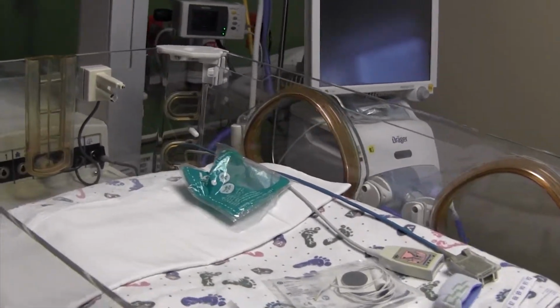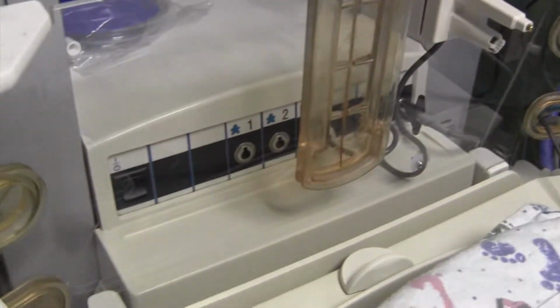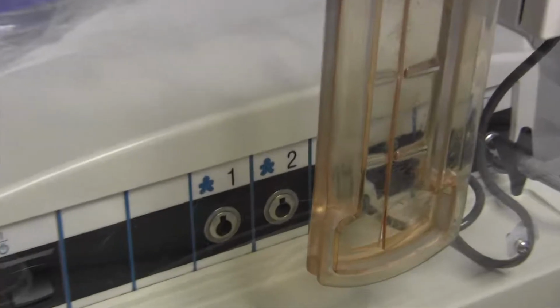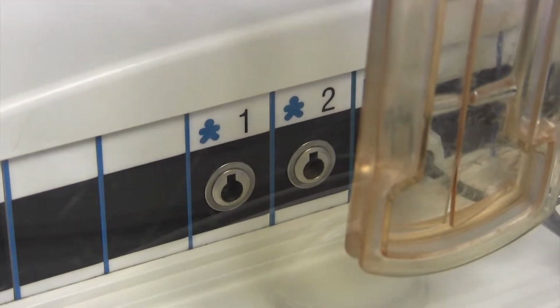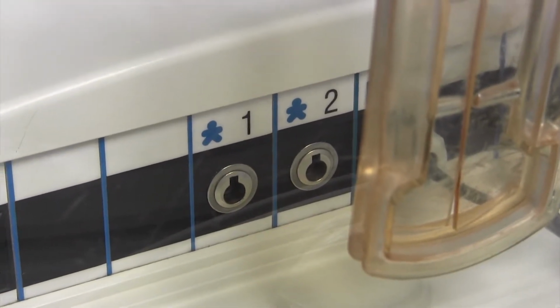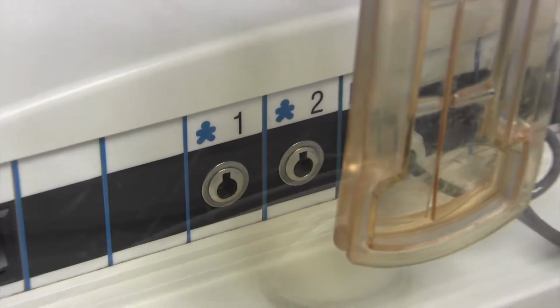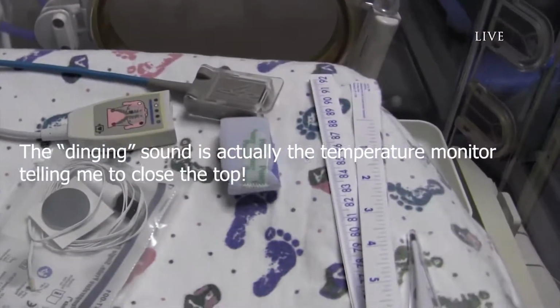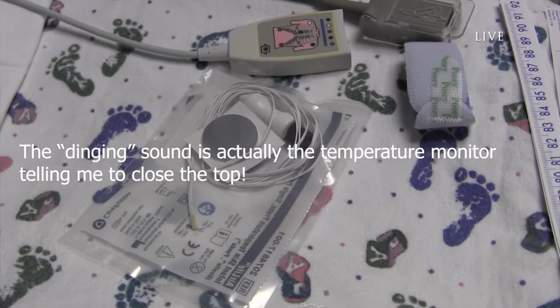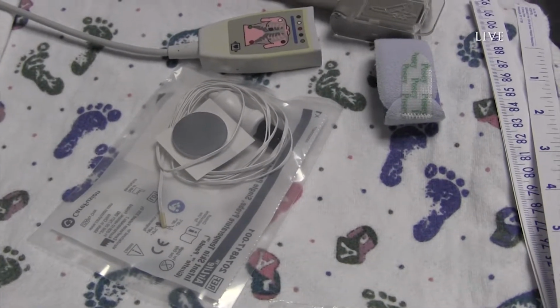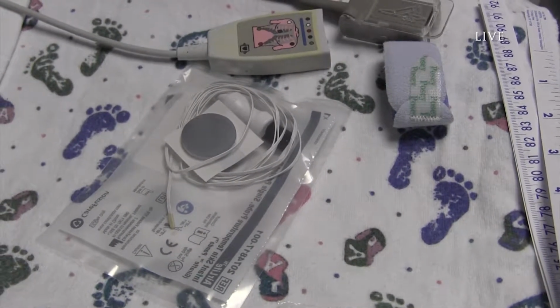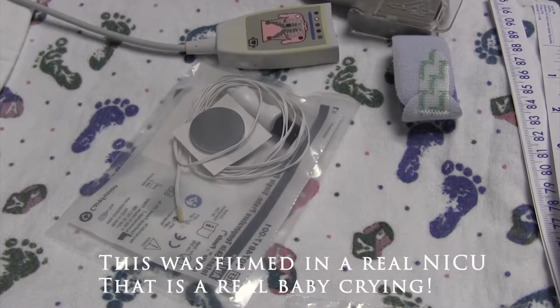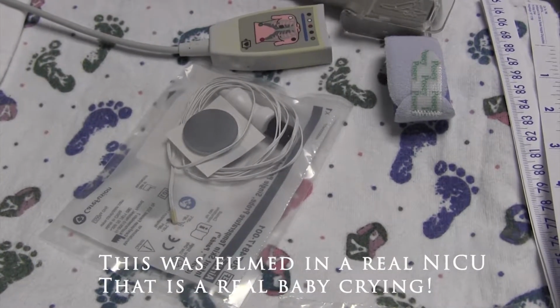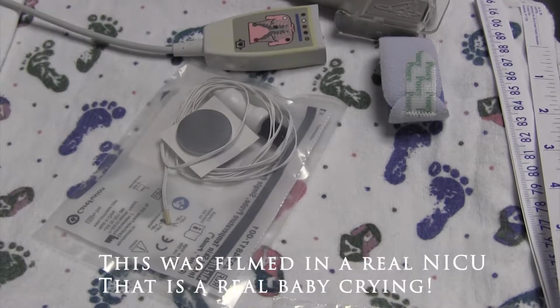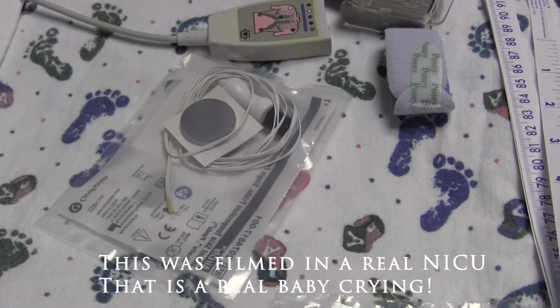The other thing that you'll notice is that there are a number of ports, and I'll zoom in on that for you, that you can connect monitoring devices to. These can include things like a temperature monitor, and that you can see right in the middle of our setup here. There's a little probe that would plug into that port, and that's placed on the skin of the infant, and that allows the incubator to have information so it can auto-adjust to keep the temperature of the infant stable.